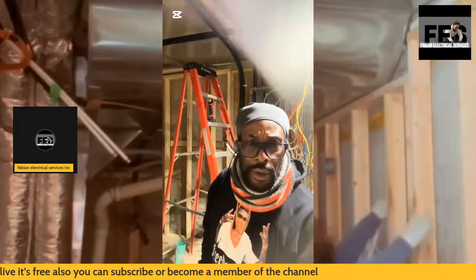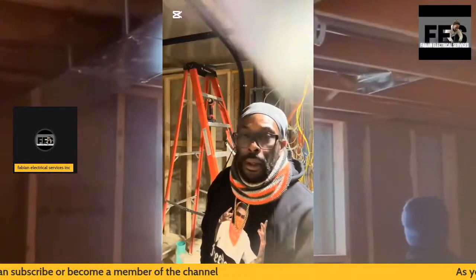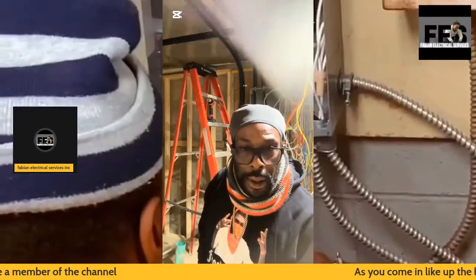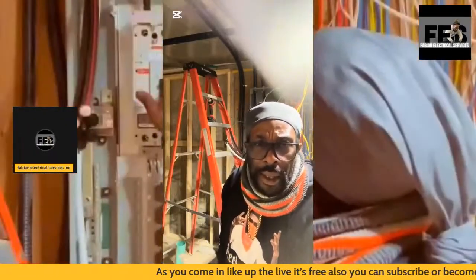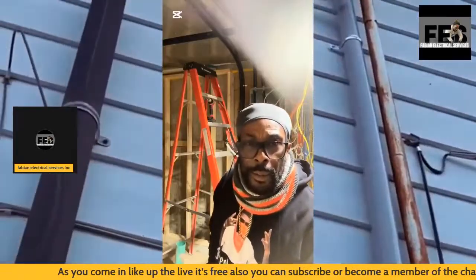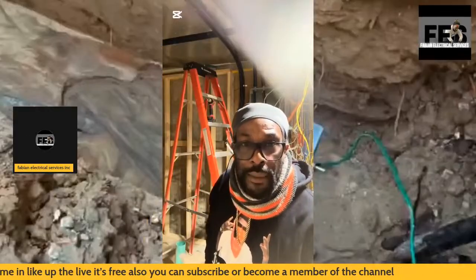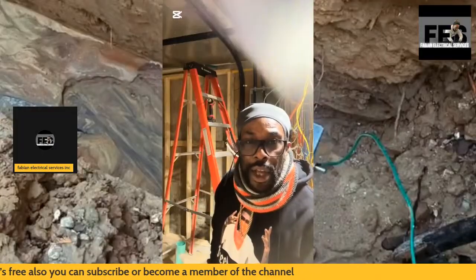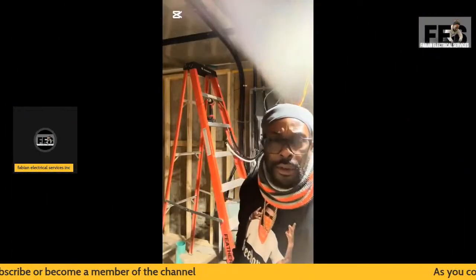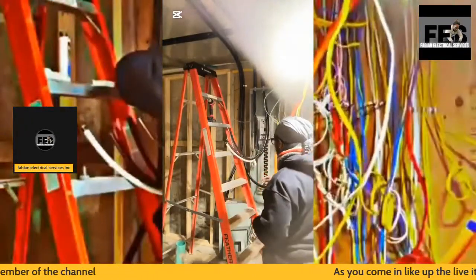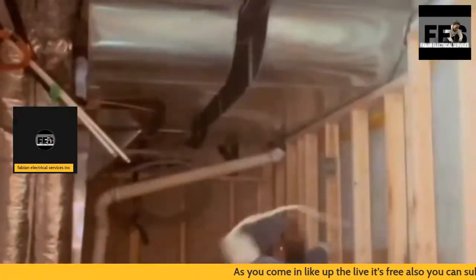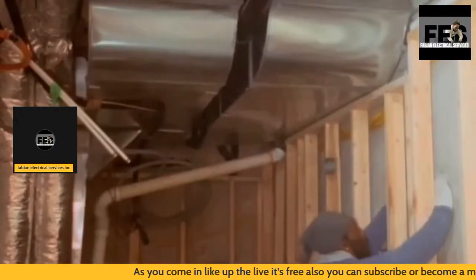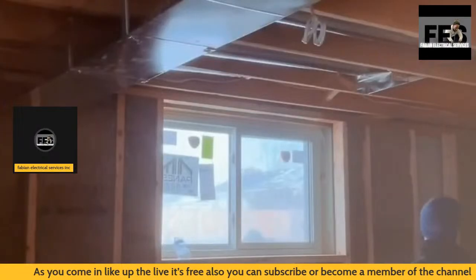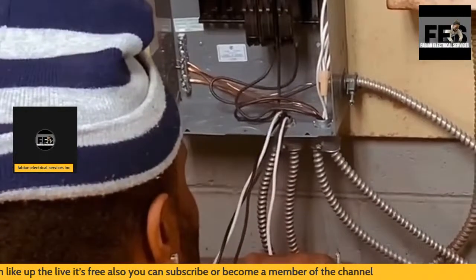For this reason, I've chosen to use TECK cable. I did have to run two parallel runs - this is aluminum cable, not actual copper. Electrical copper wire is a lot more expensive, so I've chosen aluminum, which is cheaper, gets the job done, and isn't like the olden days where you had a lot of issues.